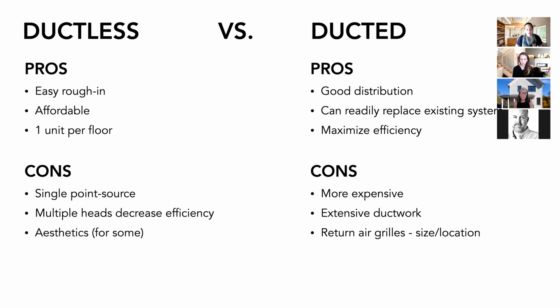Another thing that's important to be mindful of is that multiple heads off of a single outdoor unit, so if you take multiple heads and you tie them all to one outdoor unit, you are likely to see an efficiency drop in the overall performance of the unit. So you might get down to more of the 1 to 2 realm of a coefficient of performance, or in extreme cases at 1 or below. So it's important to make sure that the system is designed appropriately for the efficiency that you're looking to get out of it. And then one drawback for some people is the aesthetics, that they don't like the big cassette on the wall. They don't like the way it looks, so they'd rather go with a ducted system to have the more simplified air vent grills that might be more familiar.